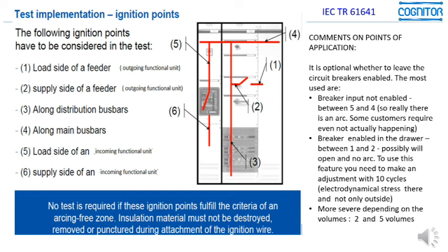There are some laboratories that sometimes say, no, you have to do all of them. This is not correct according to the standard. The standard only indicates the possible points, and the choice for doing 1, 2, 3 or all is of the manufacturer. It's an important point to remember.